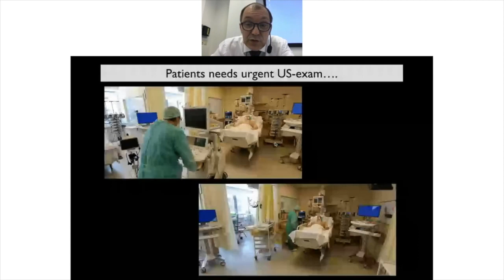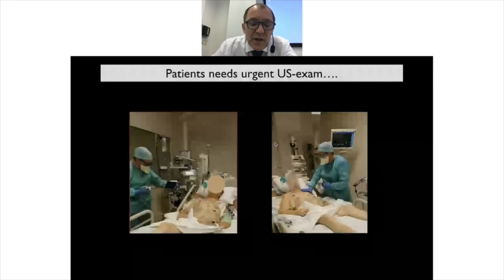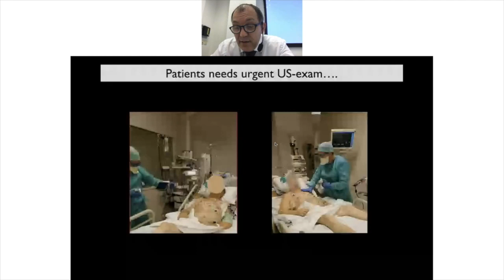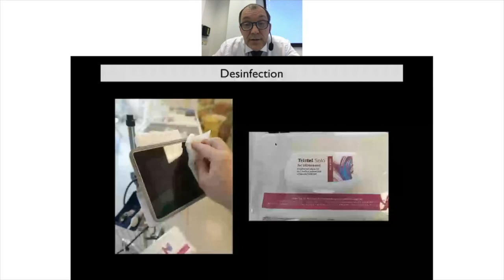Also, if you consider these high-risk infectious patients, you don't want to bend over the patient, especially not in a non-intubated patient. And then it's really convenient to take the machine, transport it to the other side, and continue your exam. Also, disinfection, as already mentioned, is quite a problem in COVID patients. And as we don't have keyboards, as in these big machines, just a touch screen and only one button, the on-off button, it's really simple and easy to clean the screen or the device itself and the probe using the dedicated wipes for cleaning.